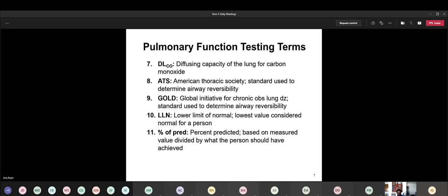Now, the ATS, the American Thoracic Society, is what most PFT labs have to comply with, the standards that are written here. And that has to do with quality control. If you have a PFT lab that does a lot of these tests on a daily basis, every lab has to start off by calibrating all their equipment at the beginning of the day, before they start seeing any patients. And your calibration has to be tight, meaning that the numbers you get should be really, really close.